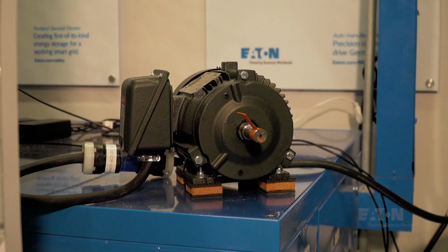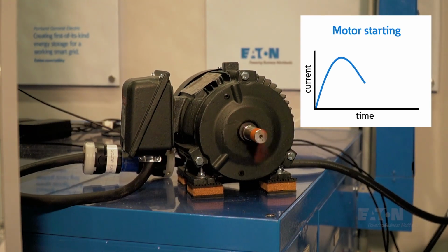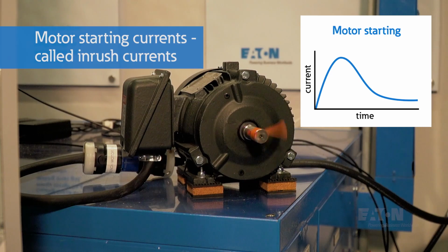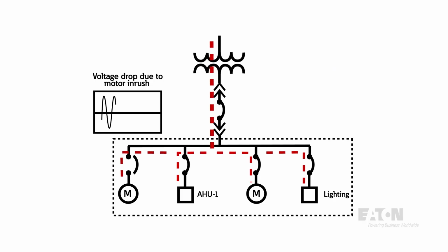Motors are used everywhere in our homes and businesses. To get a motor started, it must overcome friction and the connected load. Motor starting currents, usually called inrush currents, are very high, on the order of 6 to 8 times the normal operating or rated current. When this current is pulled through the impedance of a power system, voltage drops.